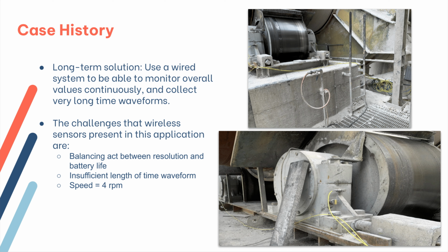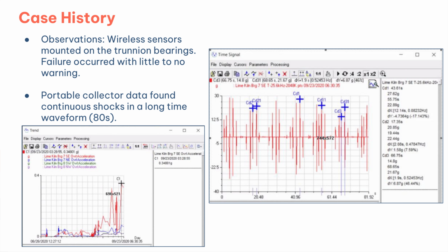It just took up a lot of the analyst's time. So it took a few hours for the analyst to take this lime kiln and all the associated equipment, meaning a few hours out of his day that he's in a hot, dry, dusty environment where it would be better to have an online system being placed. And it takes a long time due to the length of the time waveforms he had to collect to get good data. This was possible, though, with a portable system with the right amount of patience.